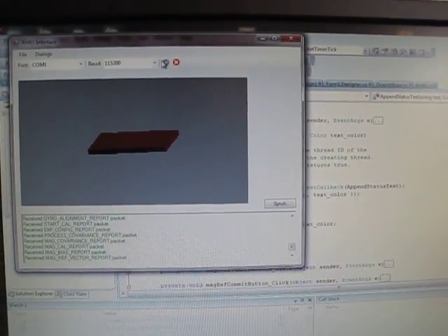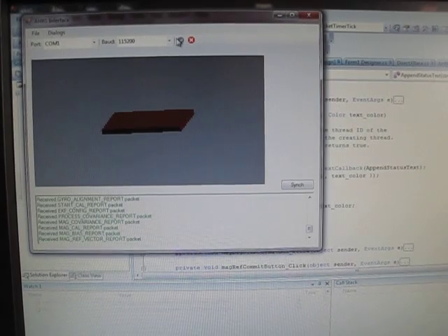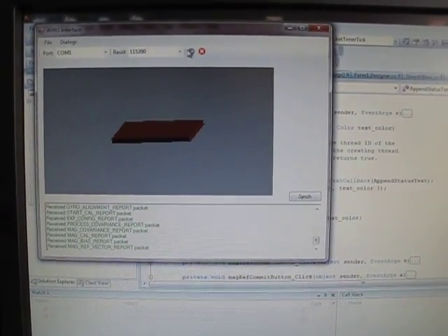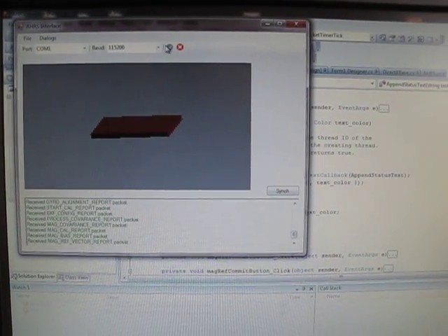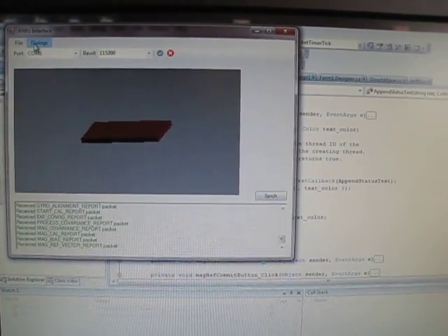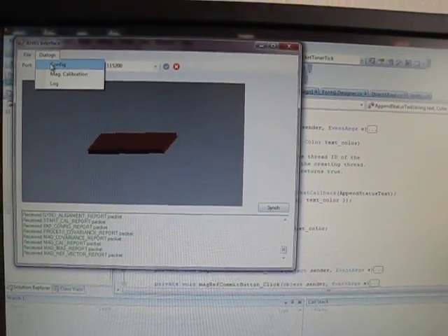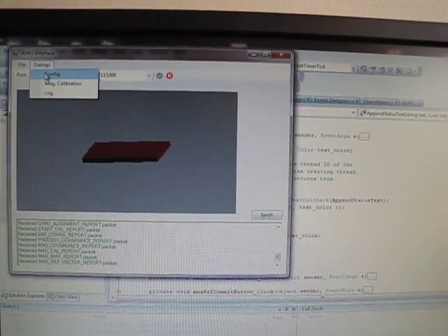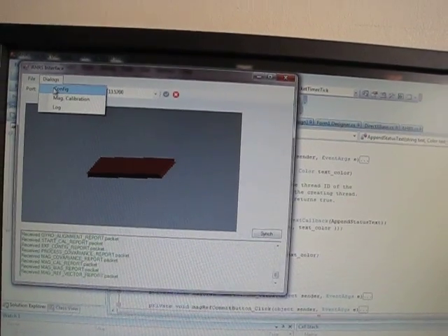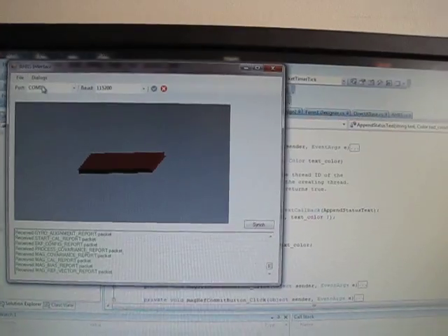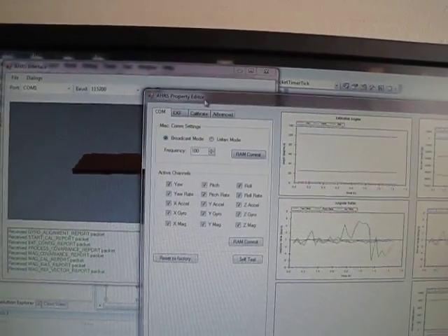Usually, under ideal circumstances, the expected output would be zero on the X and Y axes and some negative value on the Z axis. It happens, though, that sometimes after the AHRS is mounted to whatever platform it's operating with, there's some small misalignment. So that can be compensated for by setting the accelerometer reference vector.